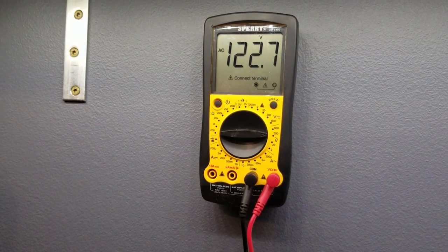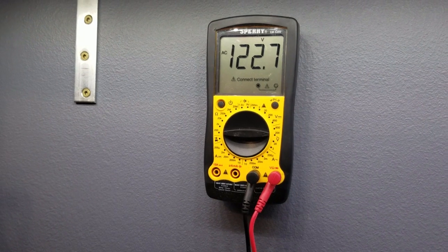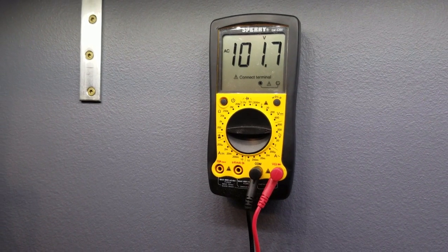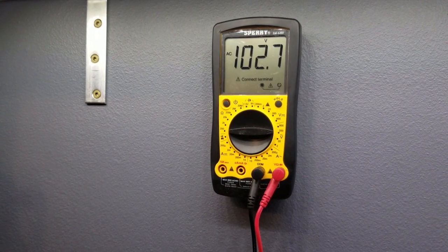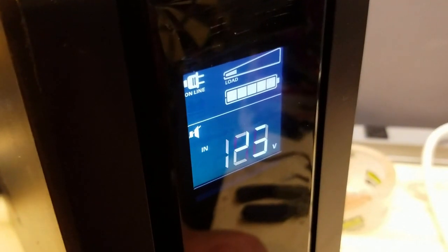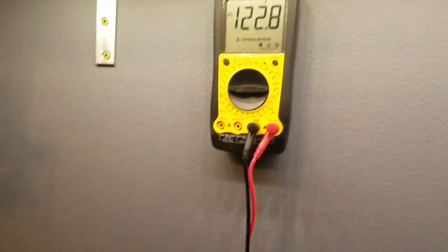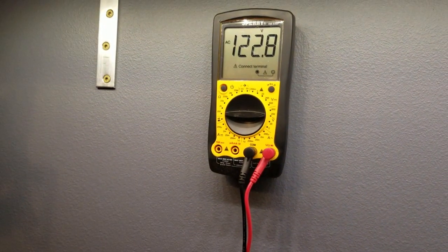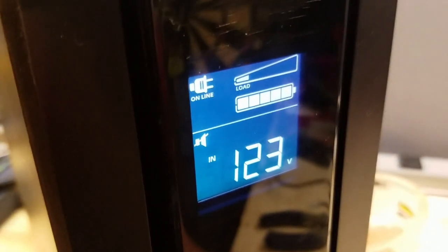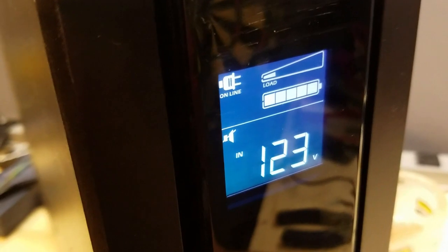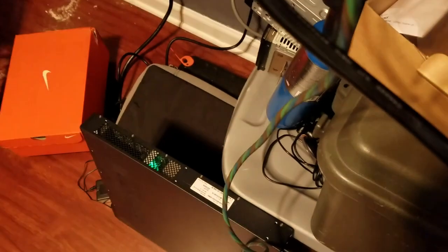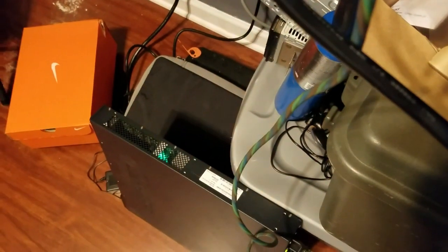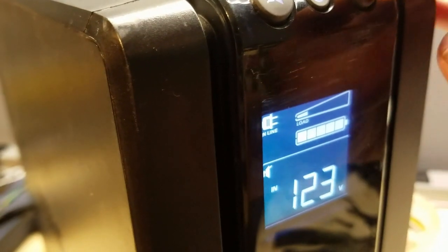Clickety-clack. So we got 122, seven, eight... oh, 102. That's weird. It said it's on battery. Okay. So it was doing a test, I guess. Alright. So screen lights on that. We're in at 123 volts, 122.6 according to the meter. Doing events. Estimated runtime. 40 minutes.